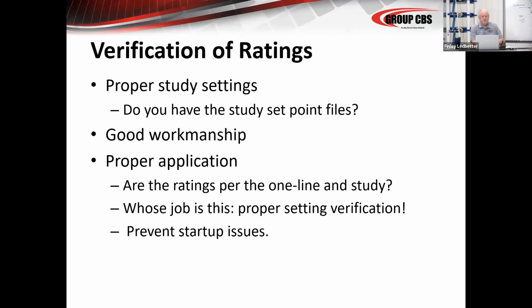Whose job is proper setting verification? Quite often the owner has an engineer involved that'll be involved in that, and the contractor is in that loop. But sometimes it will be your responsibility if you're giving that information. So you have as found tests, and what were the settings when you found them? Were they adjusted to the proper settings, or did you leave them in those as found test conditions?